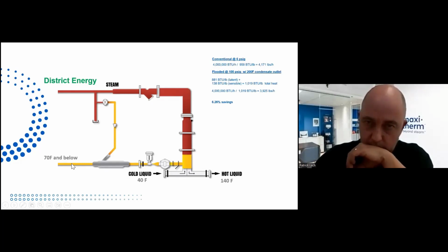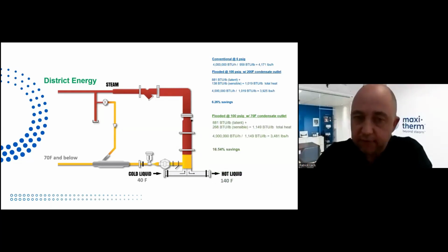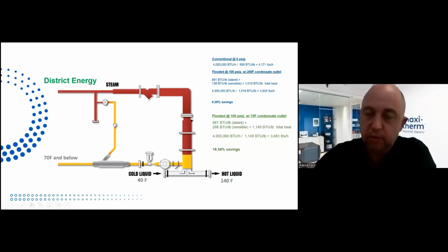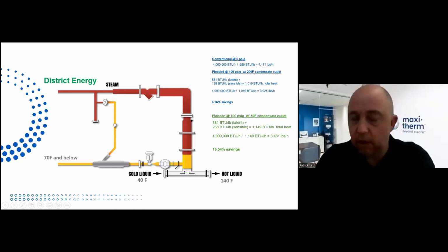No quencher, right? So what will be the number if condensate is leaving at 70 Fahrenheit, still for a 4 million BTU load? 16.5. What will be the number if the steam pressure is 150? Well, we're close to 20% saving at the point of use. A very small footprint. And you can tell any of your customers using this technology that the building on a district energy loop, whether it's a campus or a city, will have no chimney, zero on-site combustion, no gas vent, no steam vents to the roof. Very, very small footprint.